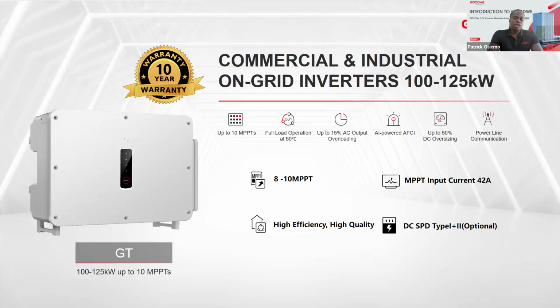Now with each MPPT, you'll get 2 string ports connected to each MPPT. So the maximum you'll have is a 20 string inverter. The full load capacity is at 50 degrees, so you'll get your maximum generation at 50 degrees. You have the output overloading capacity of up to 15%. We have AI-powered arc-fault circuit interrupters, just to ensure your strings are safe and to prevent any fire hazards on your strings. DC oversizing up to 50%. So the 100 kilowatt GT will allow a maximum of 150 kilowatt peak of panels. And it also comes with optional power line communication.